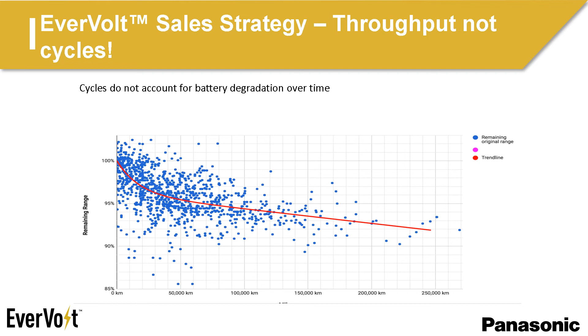For Evervolt, we will provide an energy throughput guarantee, because cycle life is not a very useful metric to gauge battery health or warranty. As mentioned before, it does not account for battery degradation over time. An example calculation would be a 10 kilowatt hour battery pack that will deliver close to 10 kilowatt hours of energy at its beginning of life, or on the first day of installation. However, on the last day, or the last 1,000 cycles, the actual energy may be closer to 60 to 80% of that initial capacity. So what happens in between? It's very difficult to determine how much energy a battery will deliver per cycle other than at the beginning of life, and this is if we define a cycle as a full 100% discharge and charge.